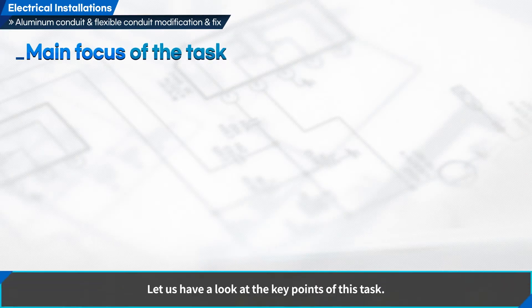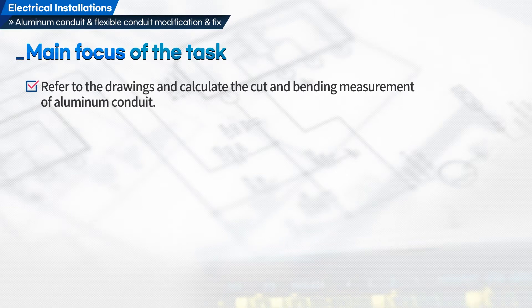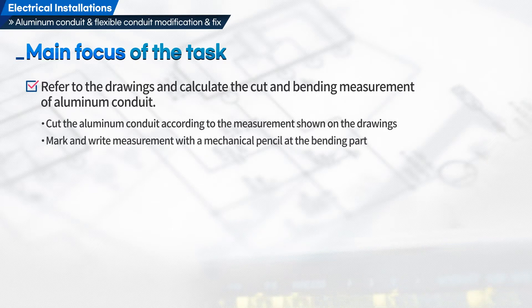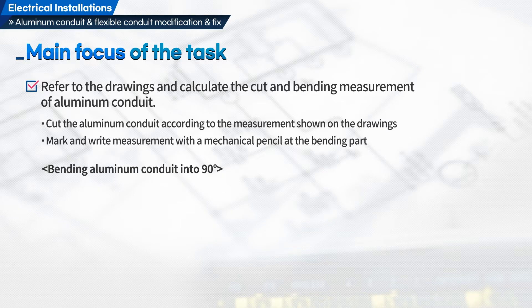Let us have a look at the key points of this task. First, refer to the drawings and calculate the cut and bending measurement of aluminum conduit. Cut the aluminum conduit according to the measurement shown on the drawings. Mark and write the measurement with a mechanical pencil at the bending part. Then bend the aluminum conduit to 90 degrees.